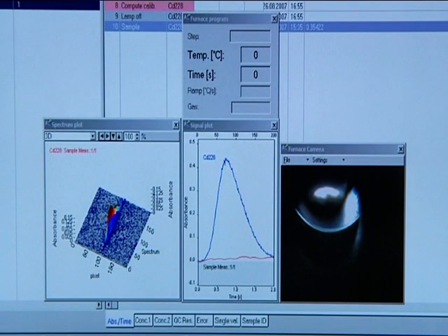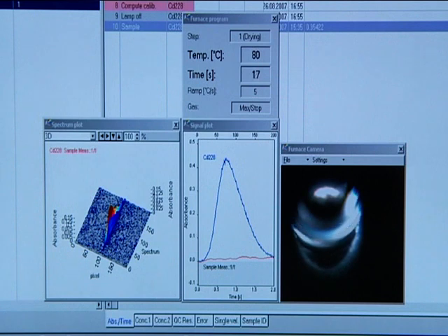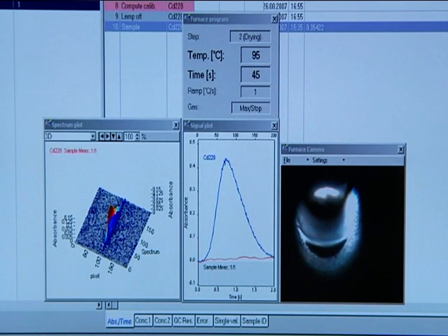An integrated furnace camera permits the sample to be observed during injection and drying. Malfunctions can be recognized better and eliminated with the now visible spectral information. The simultaneous automatic background correction is the most sensitive correction method of the AAS.